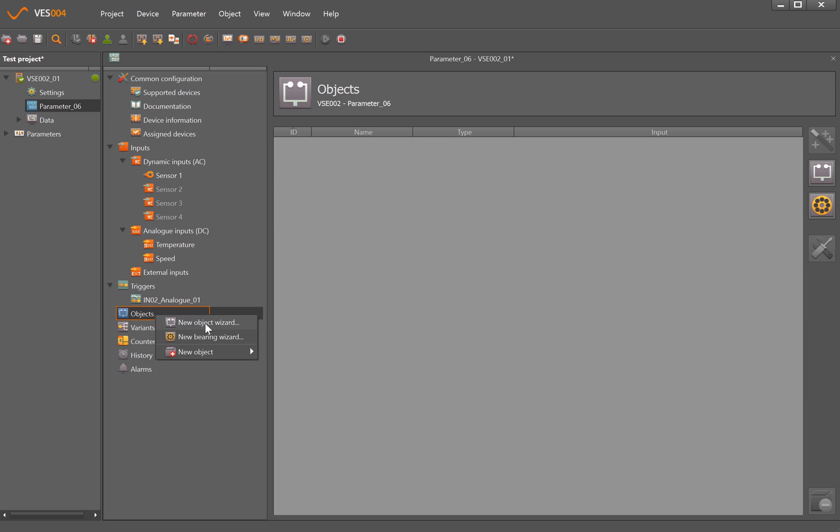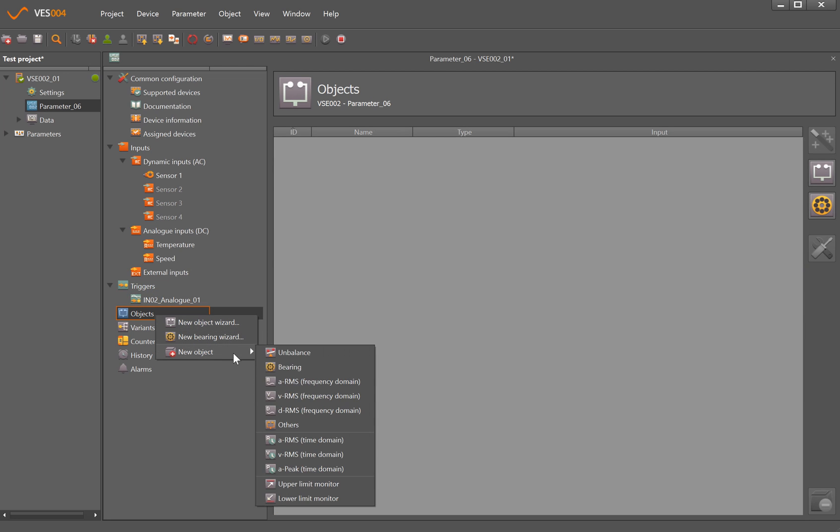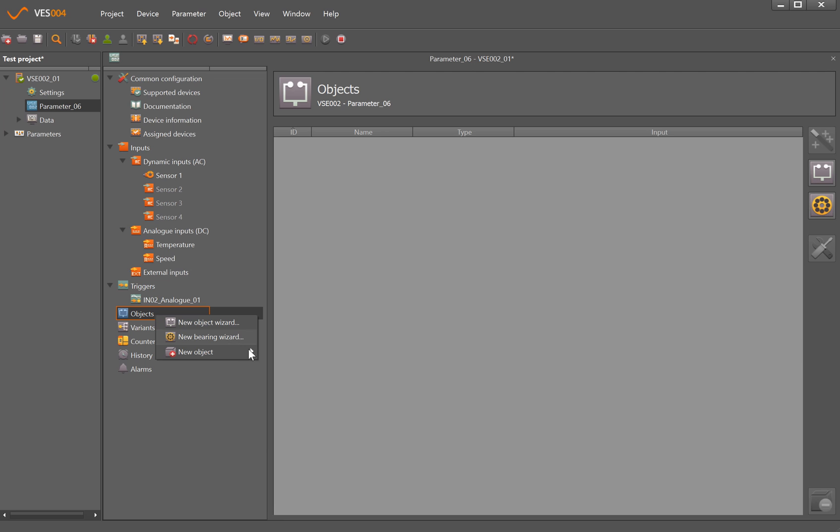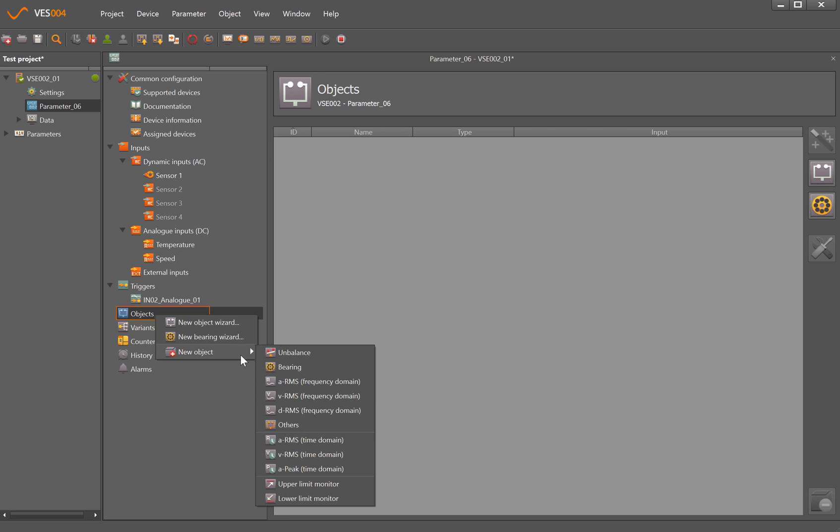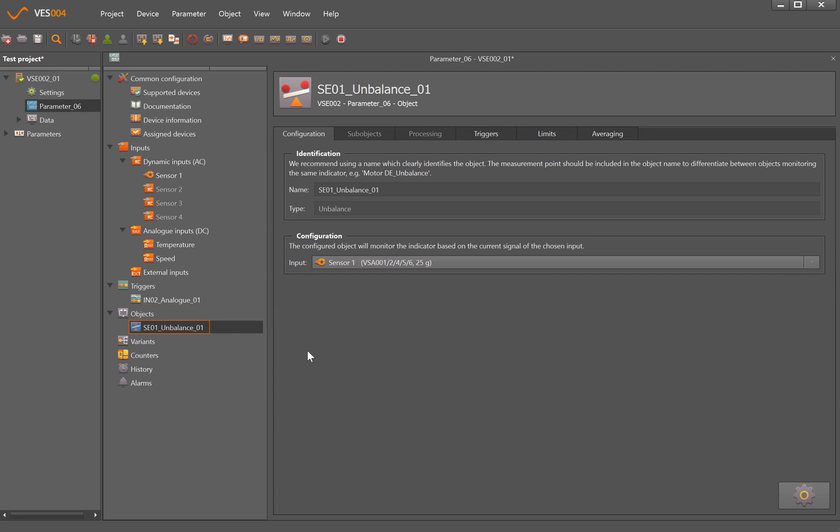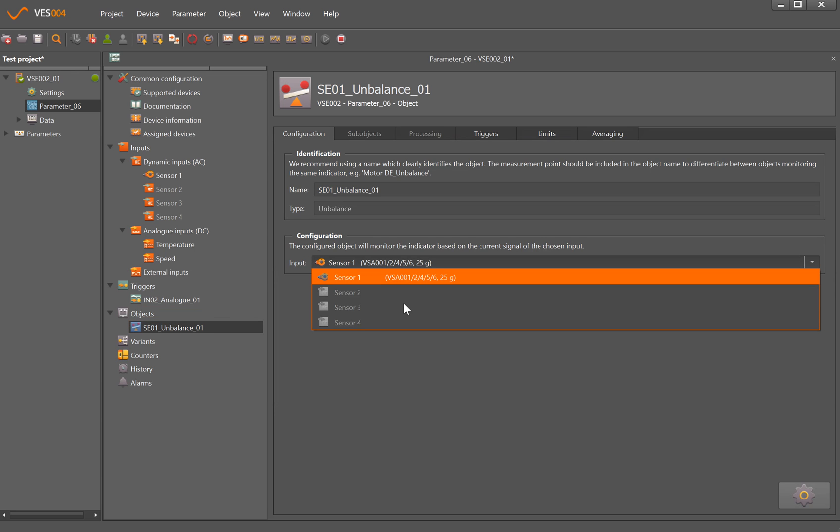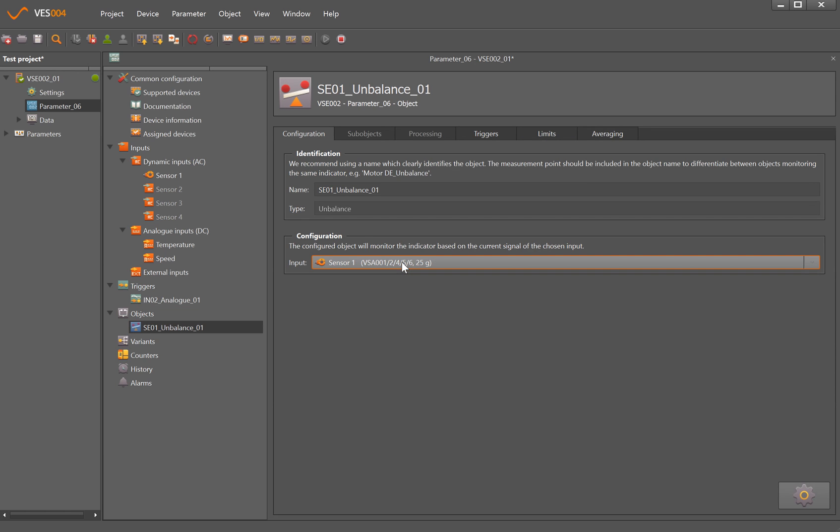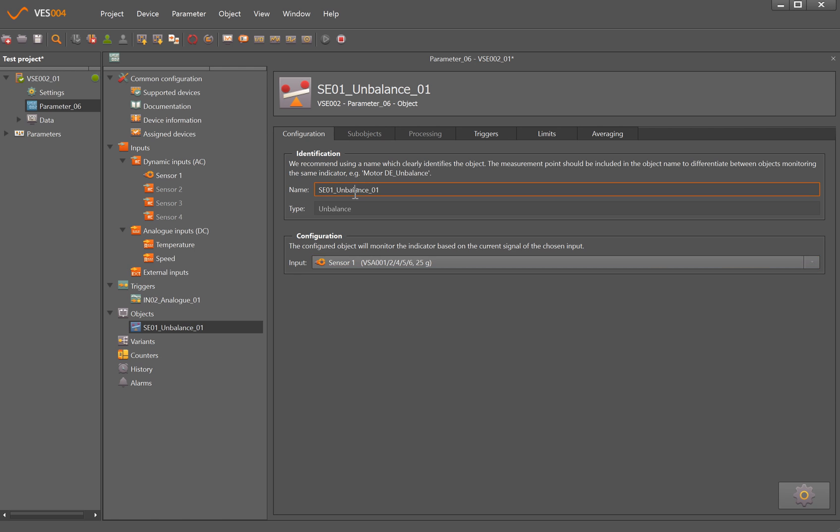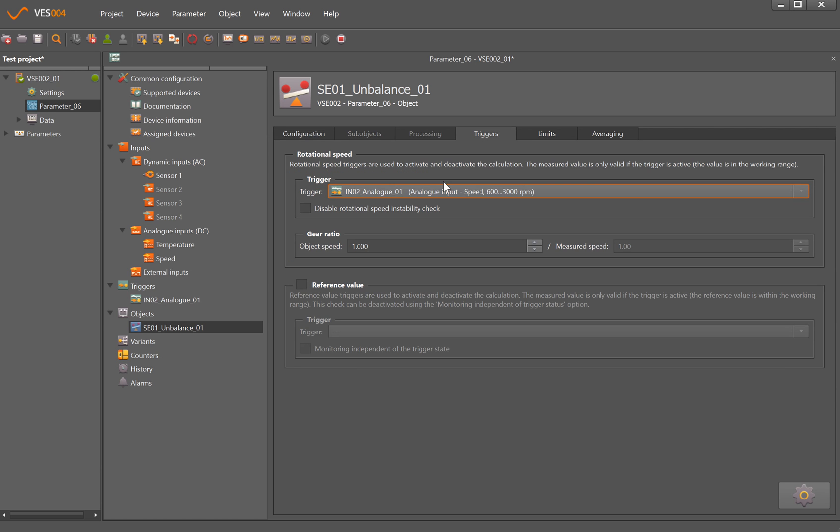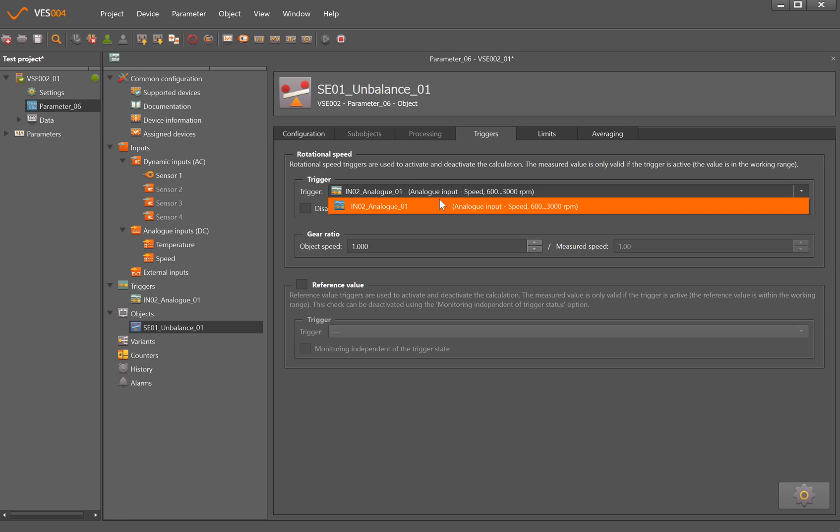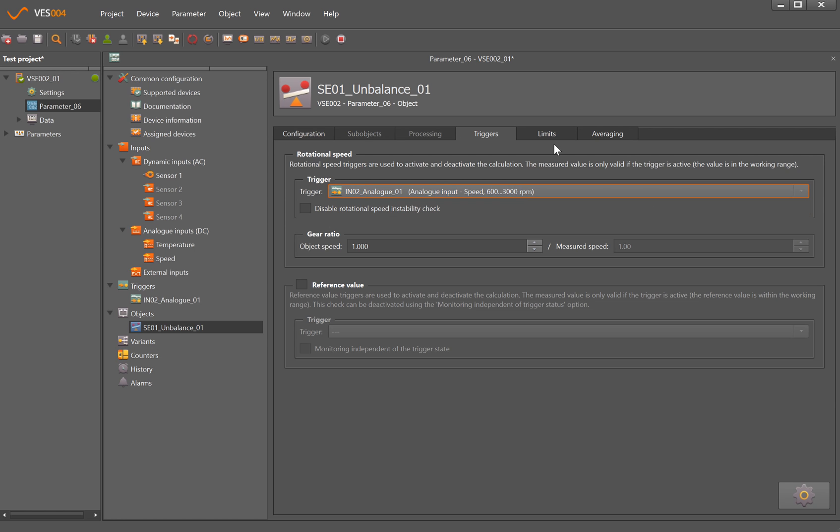So these are the actual parameters that we're going to be monitoring on the machine. So if you right click we have object wizard, bearing wizard or just new object. So the first one we'll set up is an unbalanced, so this is looking at one times rotational speed of the machine. If we had more than one vibration sensor there would be a drop down box here. We would tell it what sensor this relates to, but we only have one. The name there, again, you can change if you like. And we have one trigger set up which is the speed, so it defaults to that as well. And it also puts in some alarm limits based on what this thinks, more around kind of ISO standards.